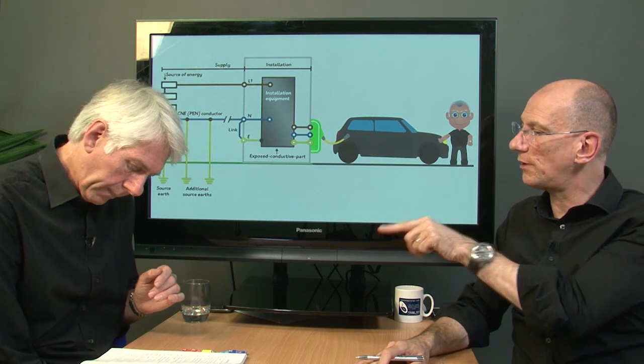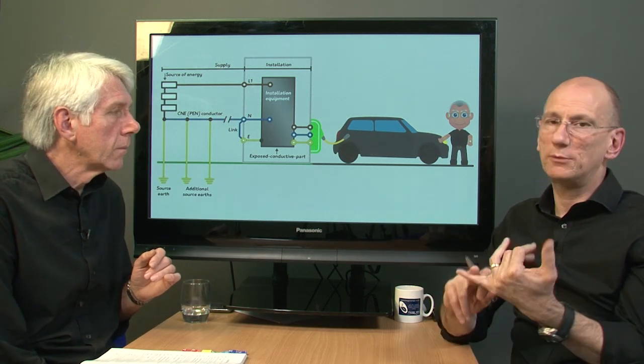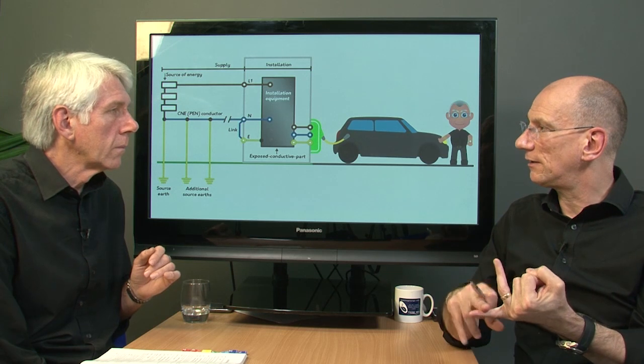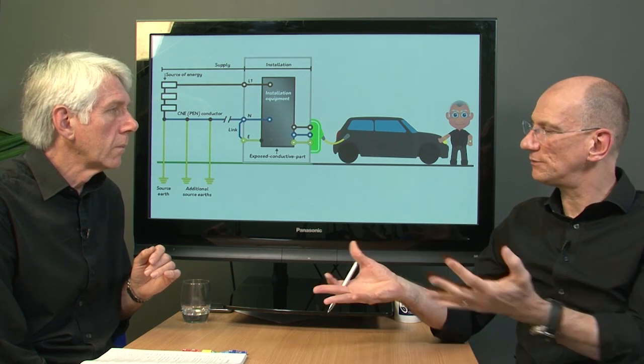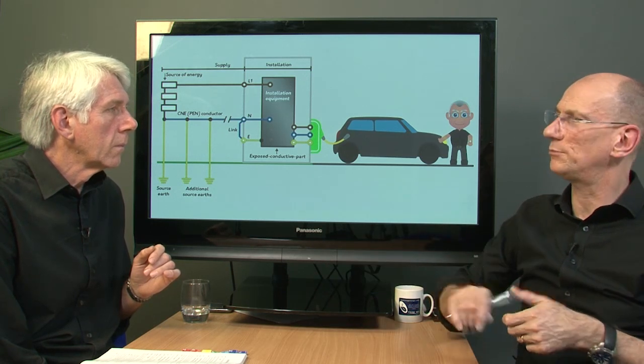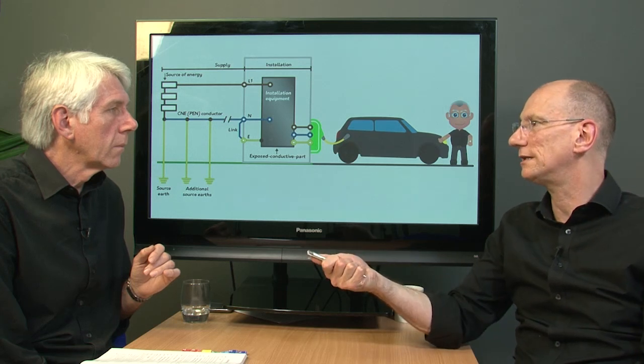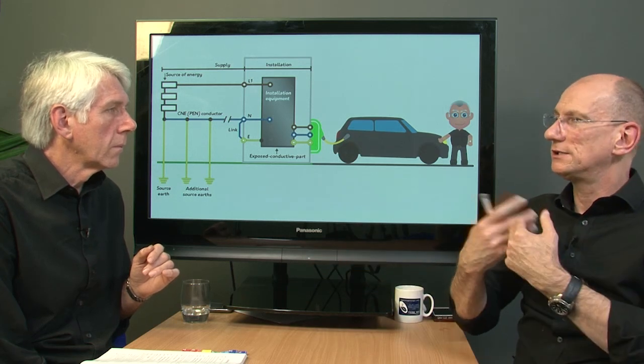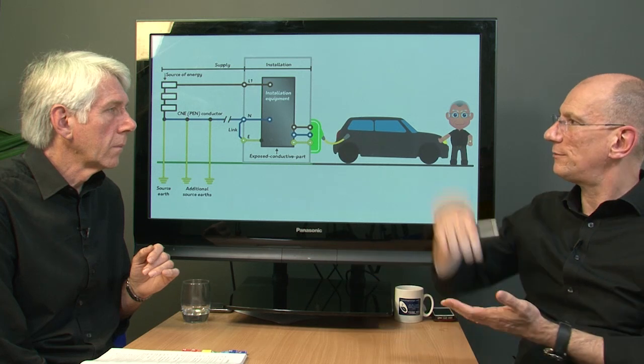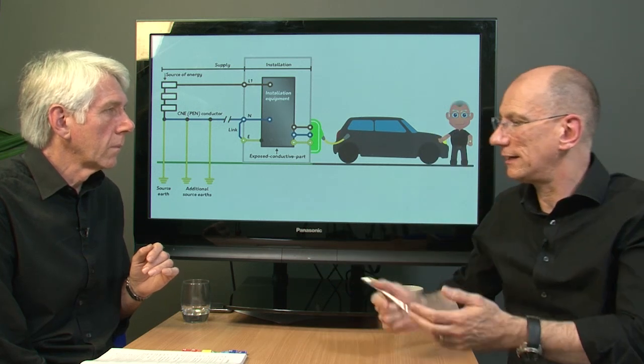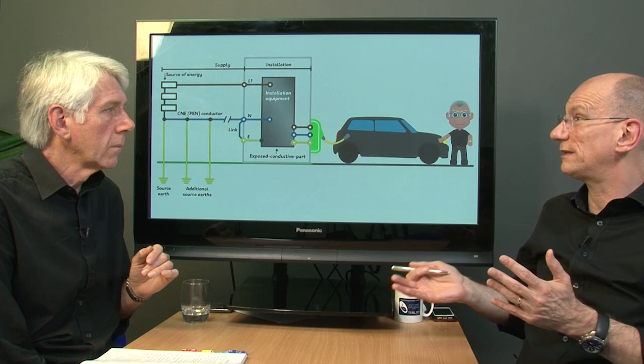Even if you are in a commercial environment, you'd want to monitor the line currents for a period of time. It's not specified, but it certainly wouldn't be a clamp meter taking three readings in a half-hour period, because time, loading, shift patterns and all that will have a massive impact on how the whole thing works over a period of months, if not a year.